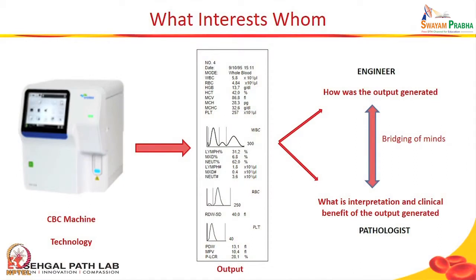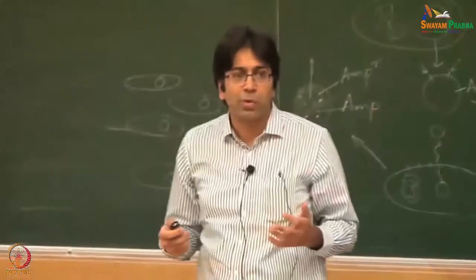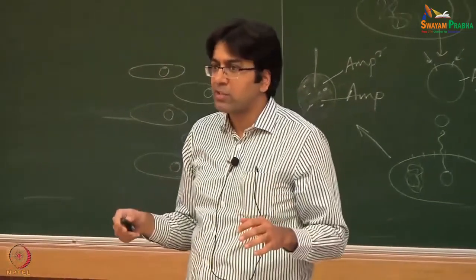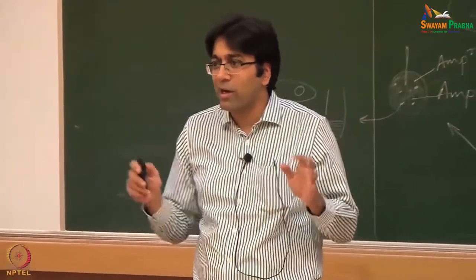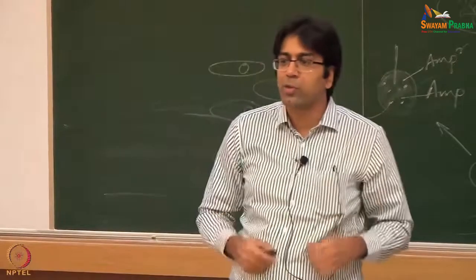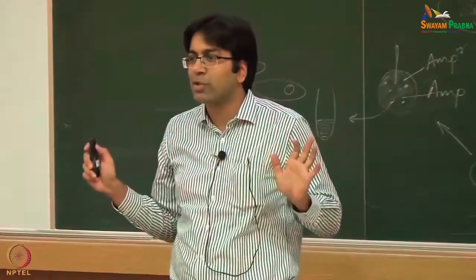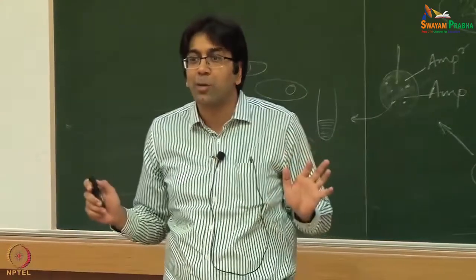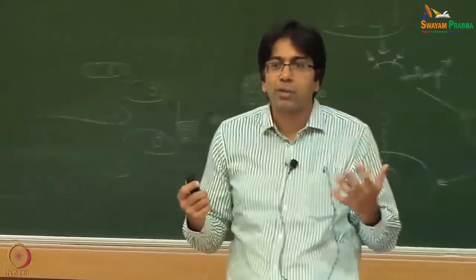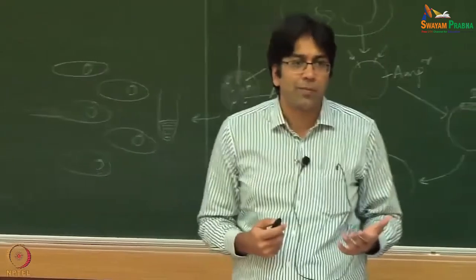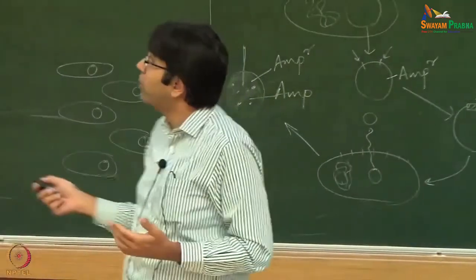For example, this is a CBC machine — the technology. And this is the output: the strip coming out from a CBC machine which tells you your haemoglobin, WBC and platelet count. The engineer wants to know how the output is generated, how to improve it. I as a doctor want to know the interpretation of this output — how can I use it for the patient. Majority of laboratorians don't understand how the instrument works or what went wrong — we call the service engineer and say 'please do the needful, I want my reports today.' This is typical, and it is not out of lack of interest, but lack of time and lack of understanding. The idea is: can we bridge this gap between engineers and doctors?